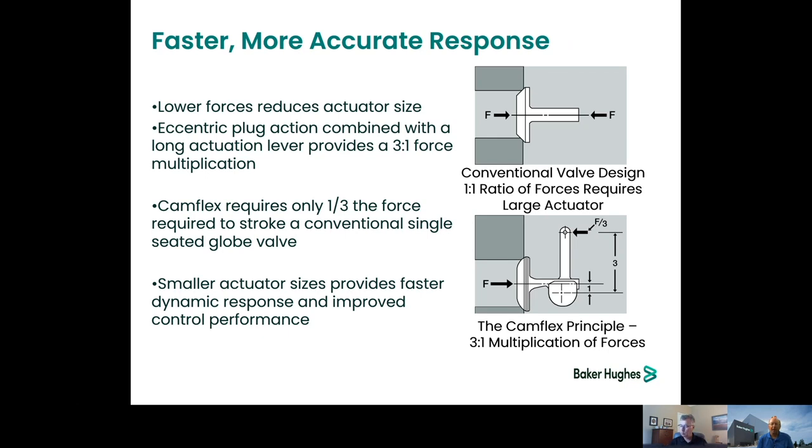And these valves typically operate using instrument air, so you're loading air in and out of that actuator case. The bigger the volume, the longer it takes to load and unload. That loading and unloading time dictates how quickly the valve can respond to a change in process conditions or a change in signal, and affects its dynamic response.